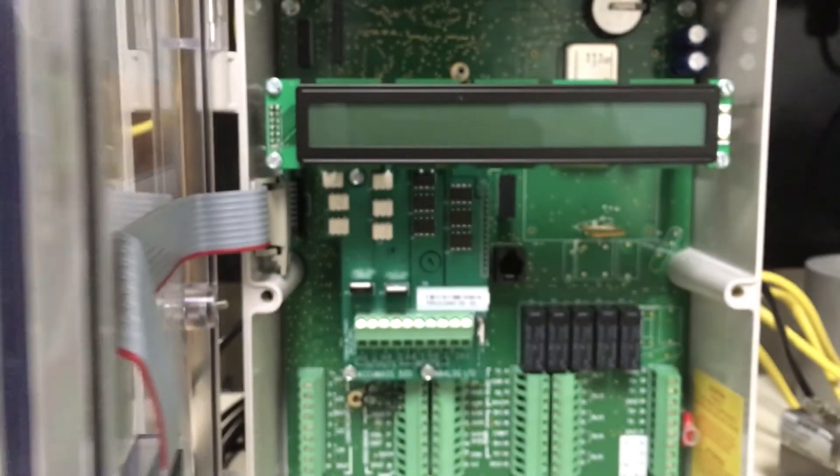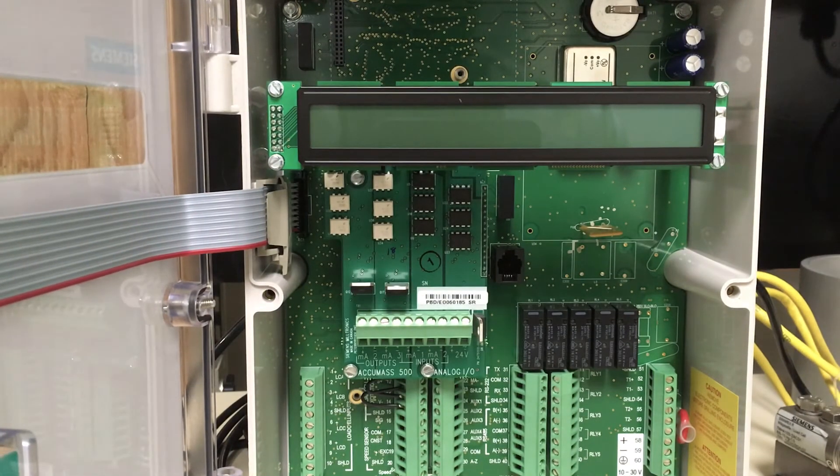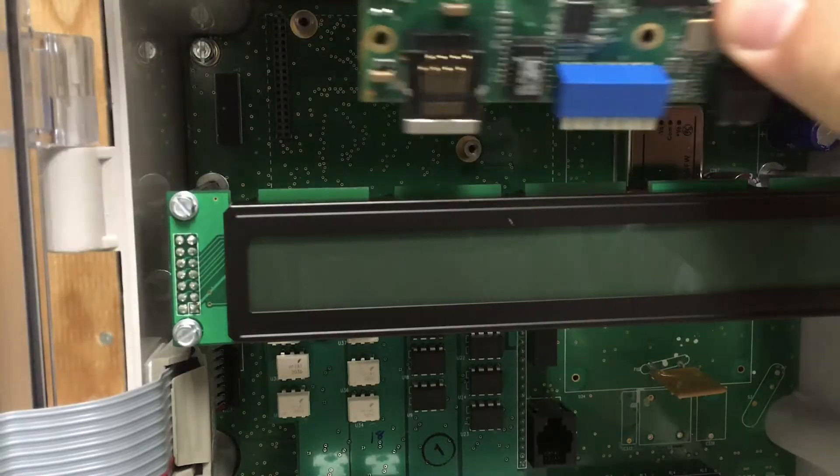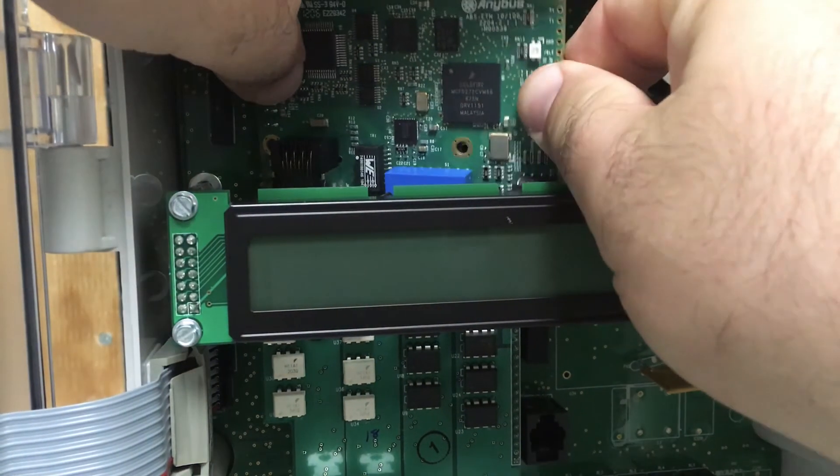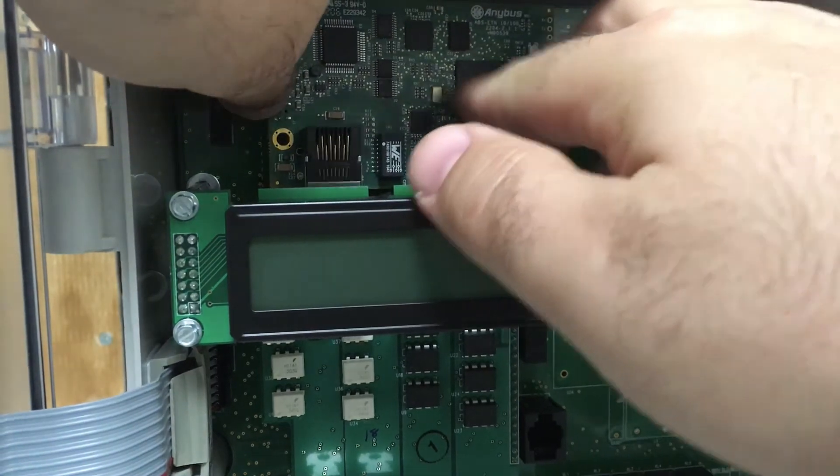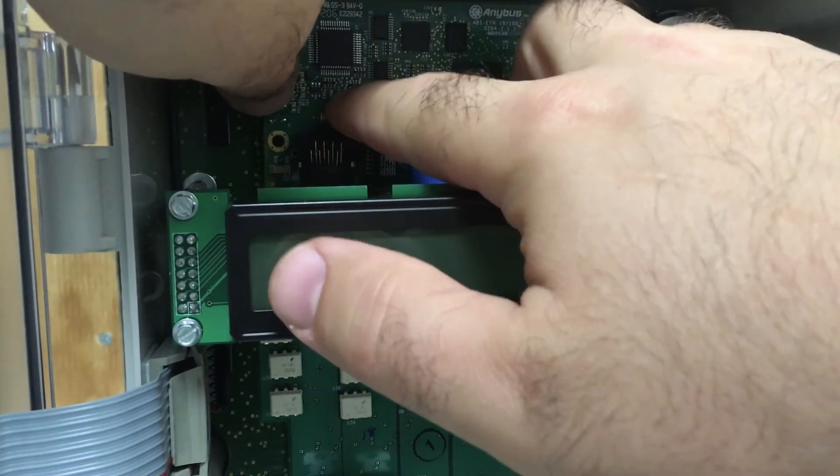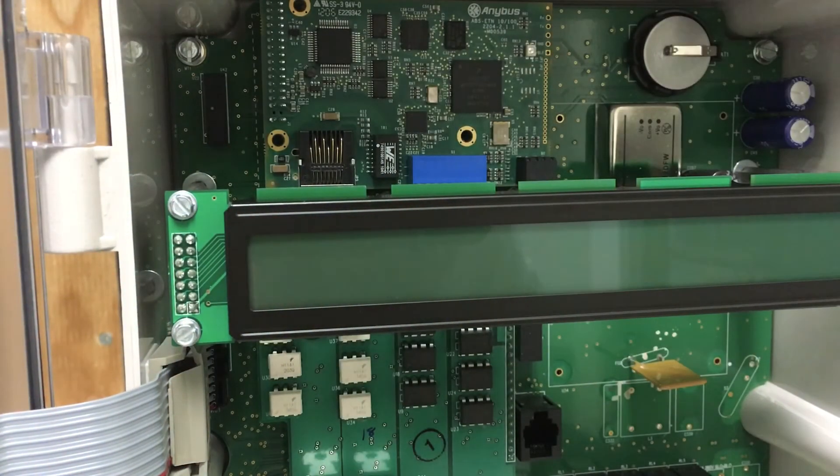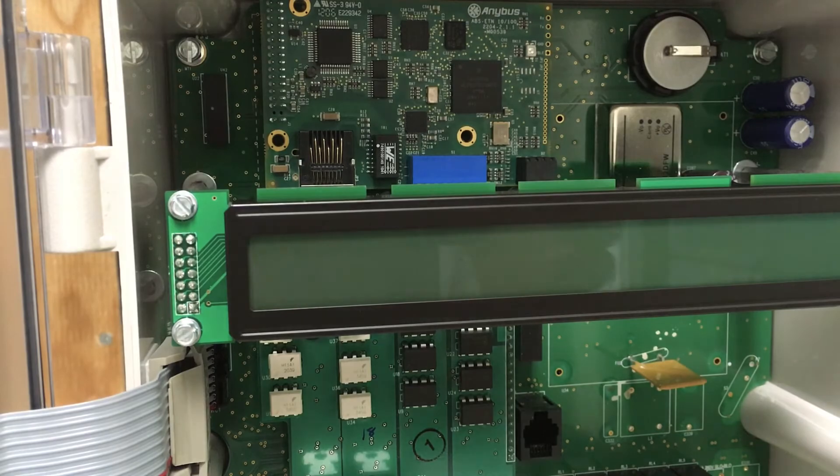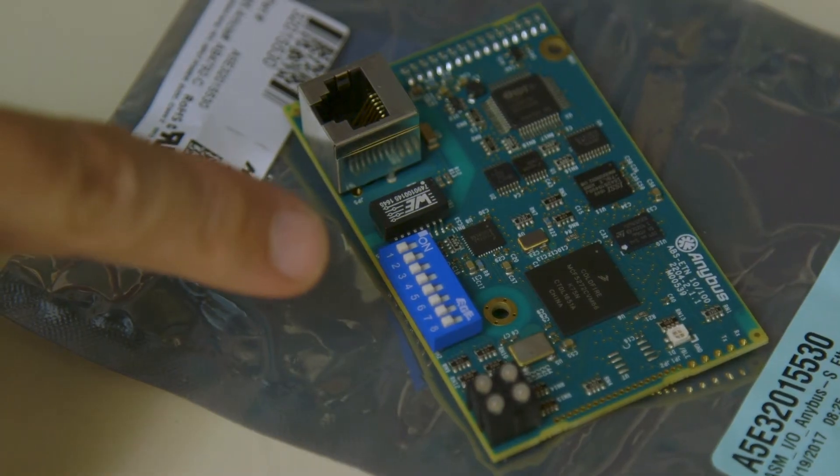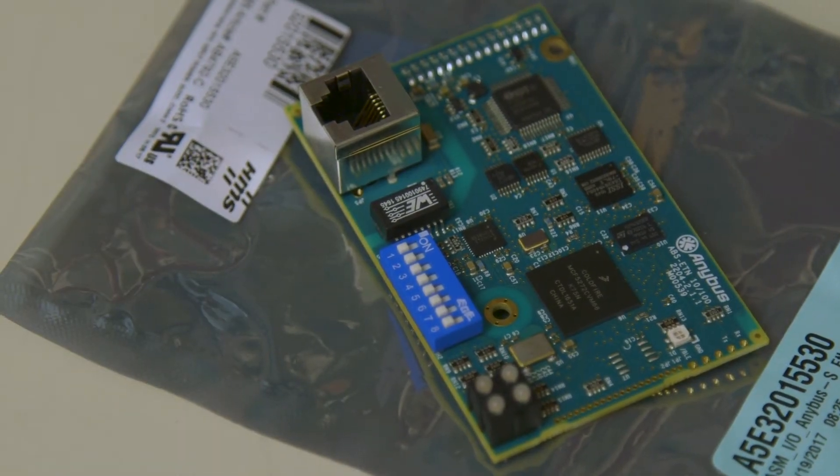If it doesn't, first power down the BW500, loosen the six screws, and open the lid. Insert the card into the BW500 SmartLinx port. Push the card onto the 34-pin connector and secure the card with the two supplied screws. Set all the dip switches on the card to the off position.